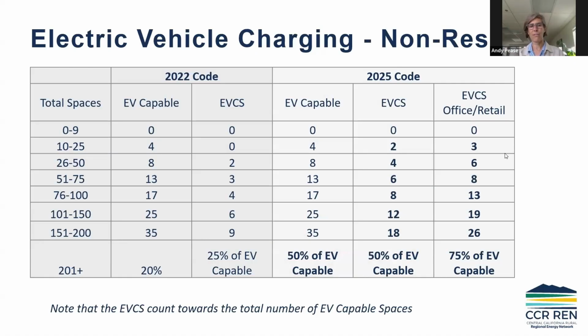Now this is the 2025 code. Again, you can see the EV capable and charging stations has now gone up. They've added a section for retail and office because they were finding they needed more actual charging stations in those scenarios, so they trigger more. If you have 80 parking spaces, you need 17 that are EV capable, but 8 of those are going to be charging stations. Or if you're in an office, you've got 13 of those, and then you just leave 4 as EV capable.